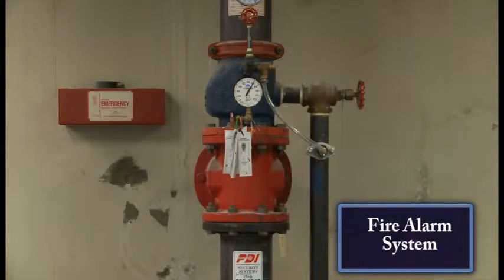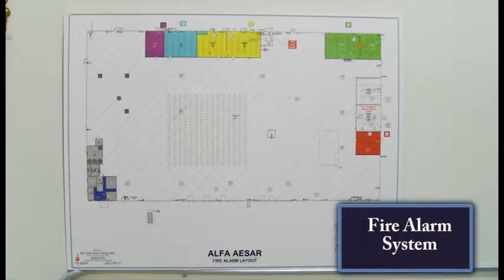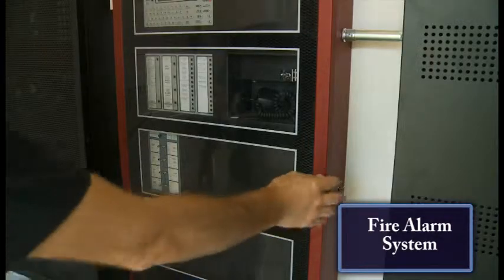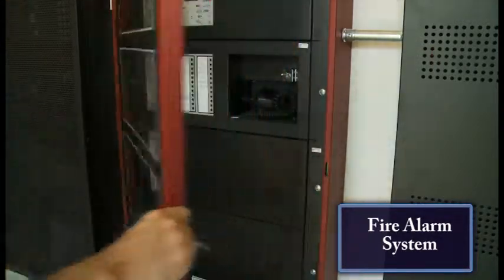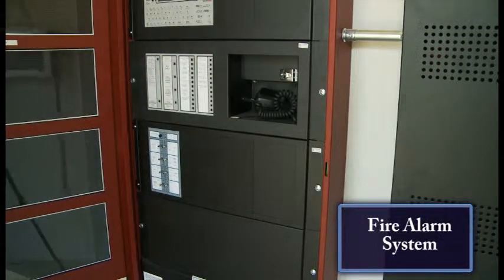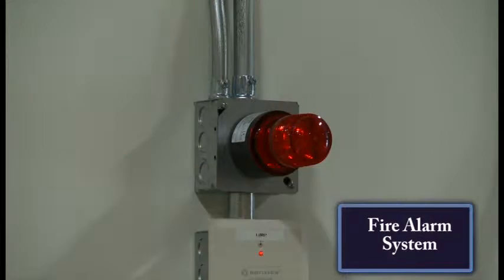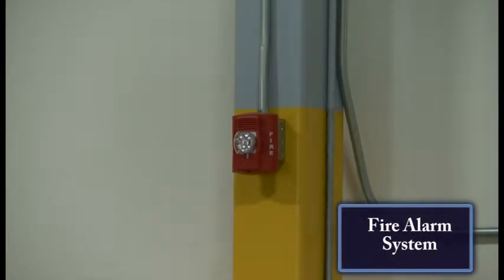The building fire alarm zoning is geographic in nature and essentially follows the building areas defined by this drawing, shown graphically on a Lexan Fire Alarm Directory located in the Fire Alarm Control Room and the AFFF-AR Tank Storage Room. The system includes a remote annunciator with test, system silence, and system reset switches behind a locked cover. The building is equipped with strobe and horn strobe notification appliances.